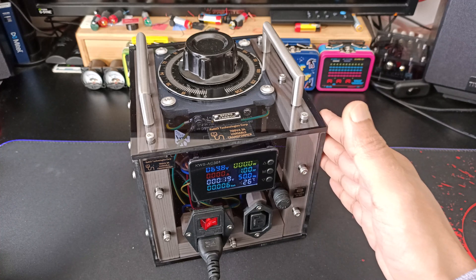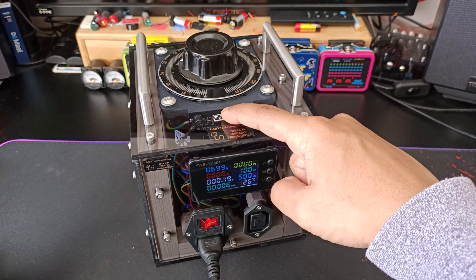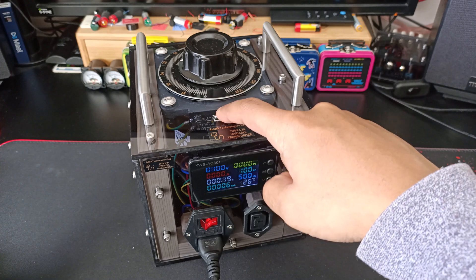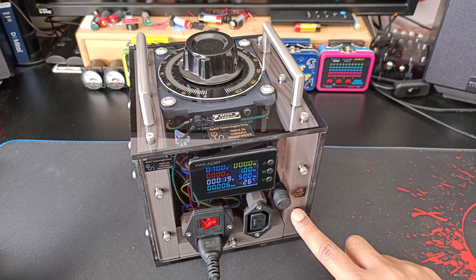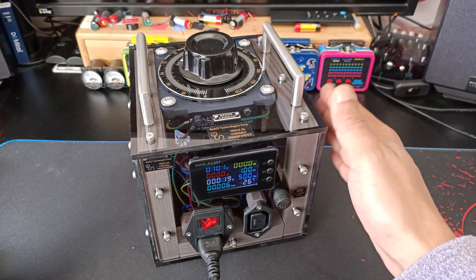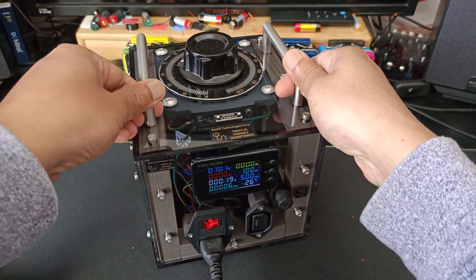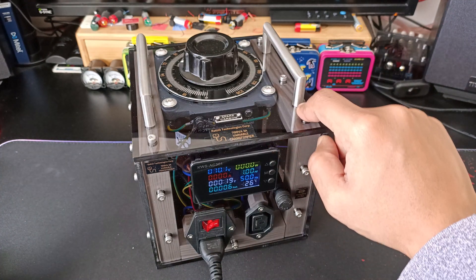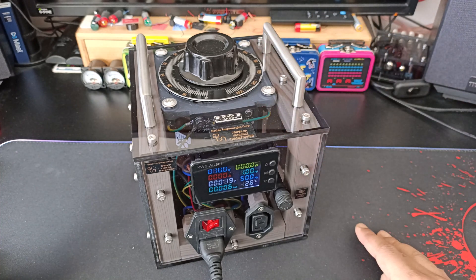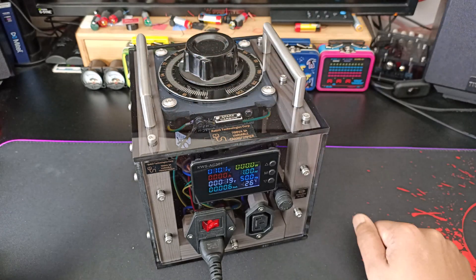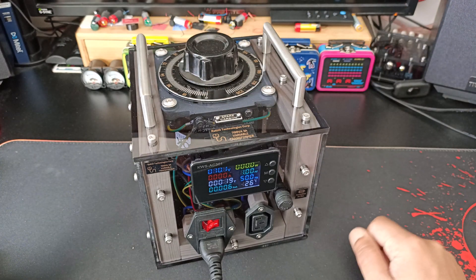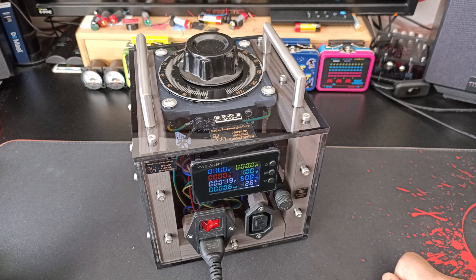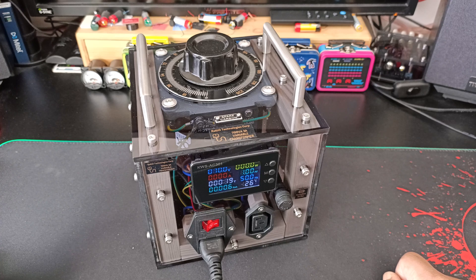It's got a perspex enclosure so the device can be examined without opening it. There's an extra carbon brush holder here. All the metal fixings are insulated using pieces of wood which hold the whole thing together. So if any hot wire comes loose it's impossible for these to be touched, so these don't need to be earthed. The only things earthed are those touching the transformer frame. All the internal connections are done using screw terminals or ring connectors with serrated washers.